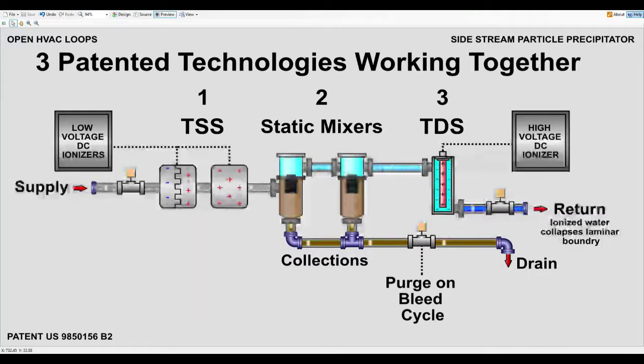This process is accomplished in three steps. First step: Electrocell addresses and eliminates 98-99% of all suspended solids down to 1 micron. This is done with a series of low voltage DC ionizers which flocculate and coalesce suspended solids, turning small particles into larger particles.